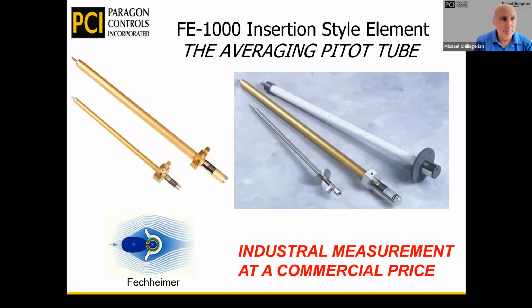It's built based upon a phenomenon that a German engineer, his name was Fechheimer, found out about in the early 1900s, where they find a total pressure or velocity pressure goes into the leading edge of a tube. But if you go 20 degrees off on either side, you'll find that you're back at just the standard static pressure. So our averaging pitot tube is basically a tube within a tube, and we set them up with the right number of sensing points based upon the size of the duct.